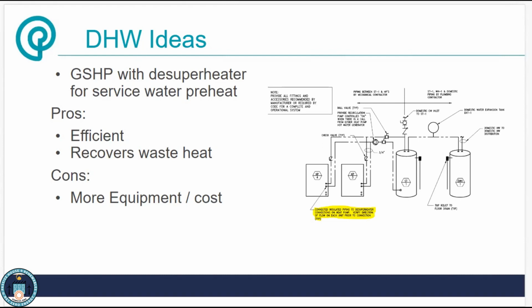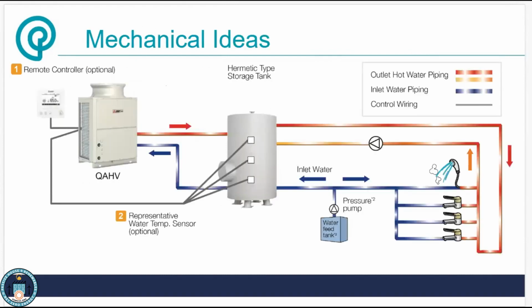On the next slide, I've pulled out another type of system. This is an image of a Mitsubishi QAHV system. It's very comparable to the Sanden or any of the other heat pump water heaters that we're seeing with the split system. And when they go split, a lot of these are going to be CO2, which is R744, and that's using CO2 as a refrigerant rather than a traditional R410A or what other common refrigerants are. R134 I've seen on a couple of pieces of equipment still.